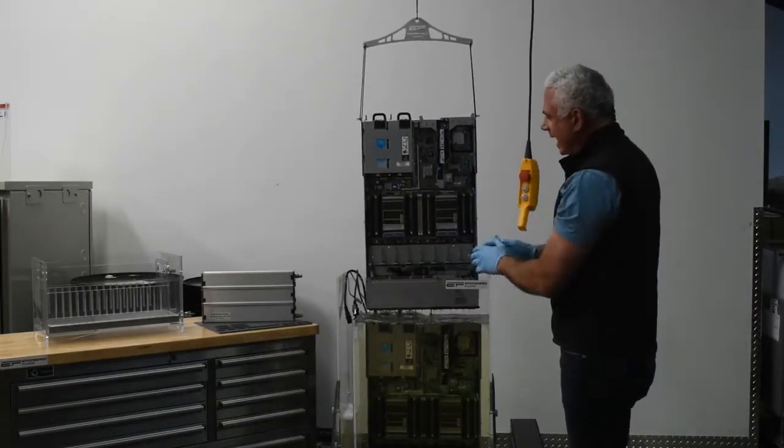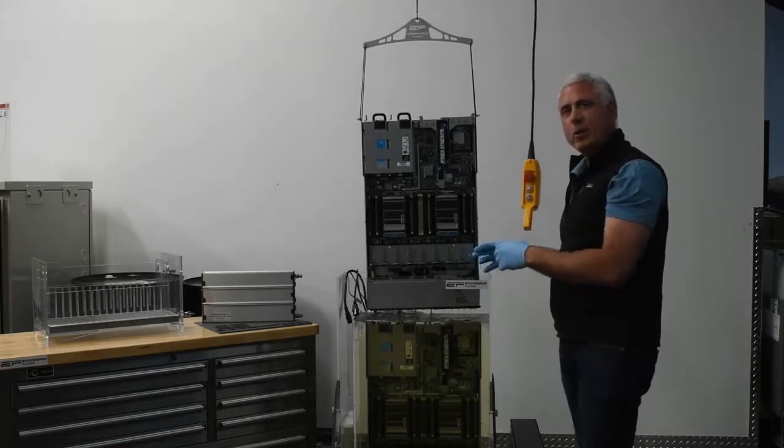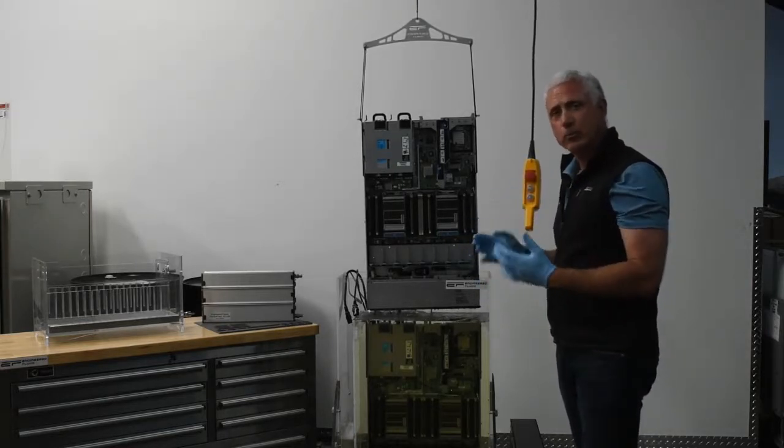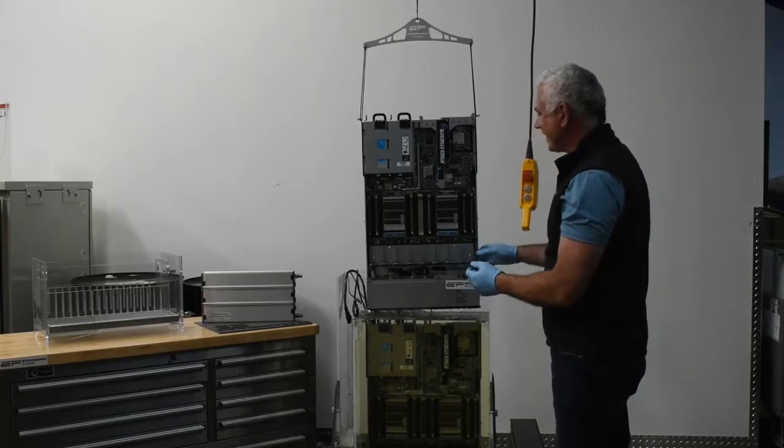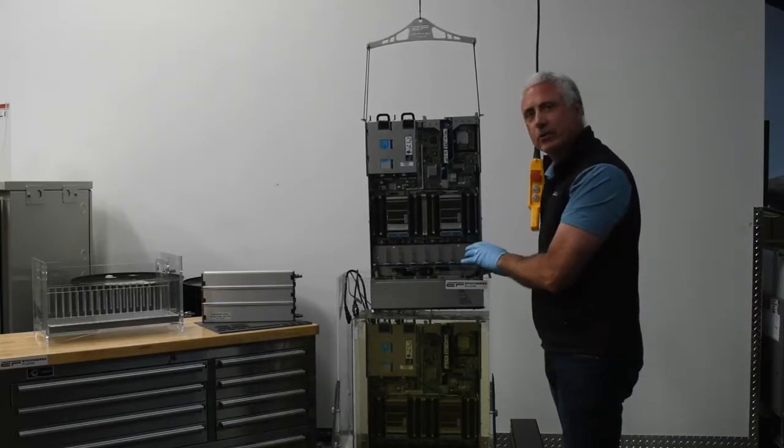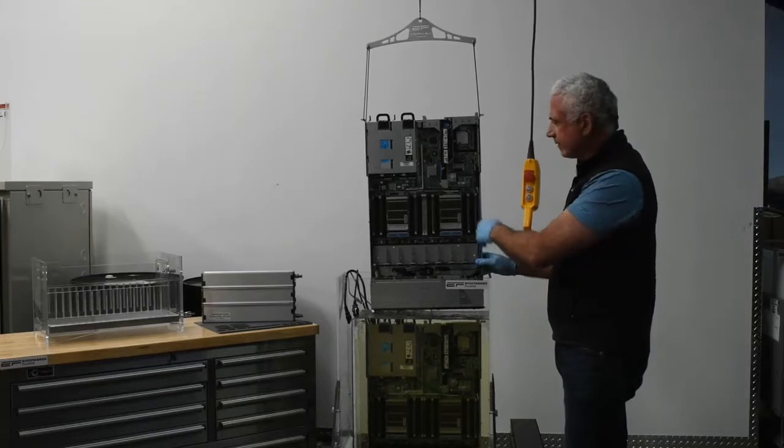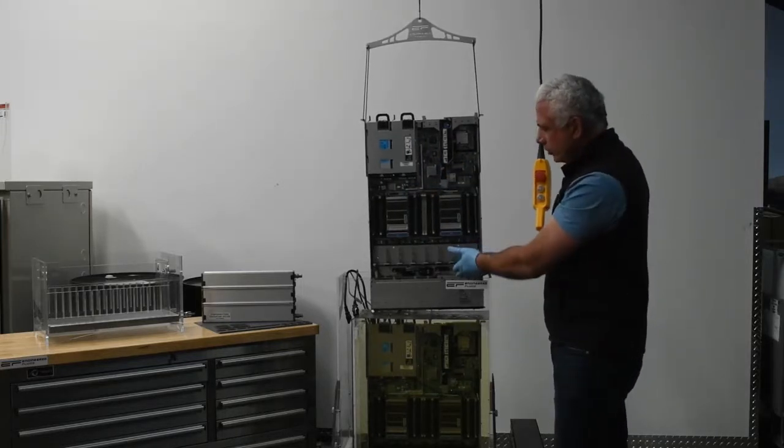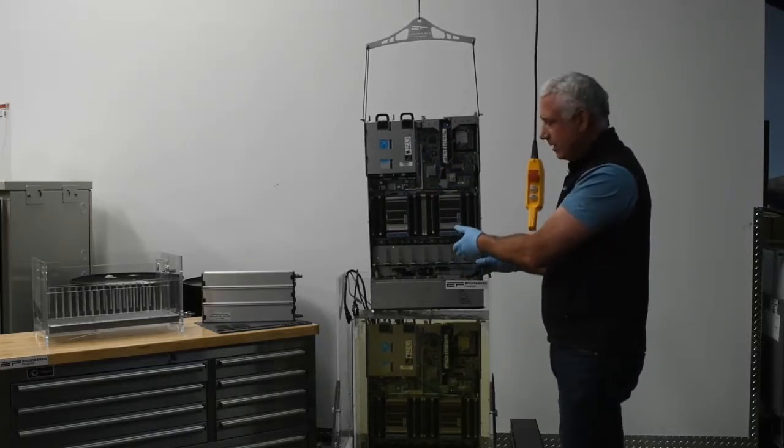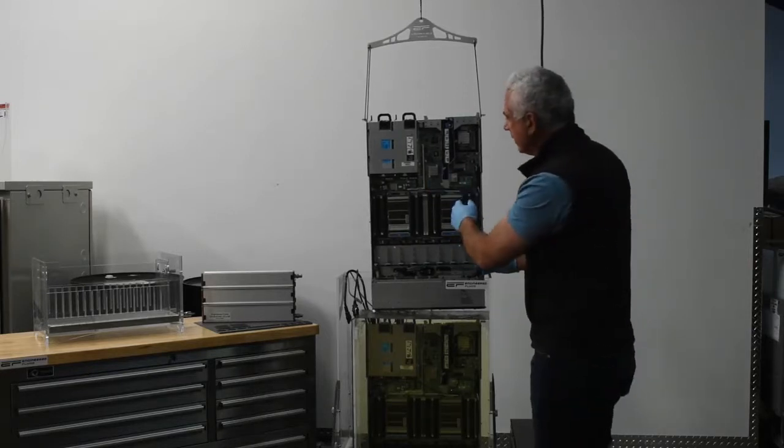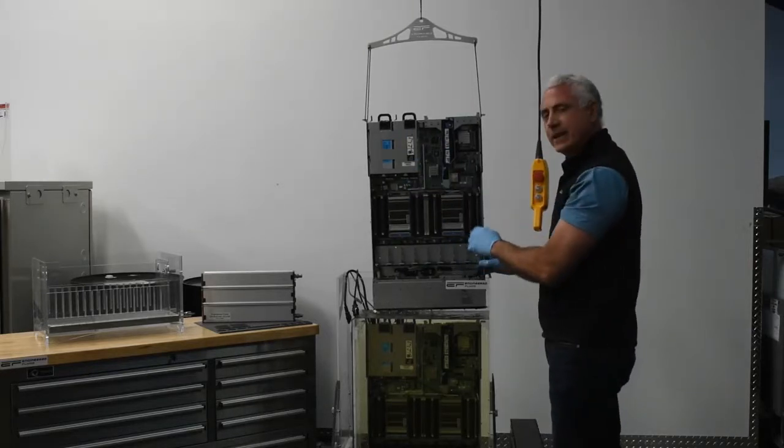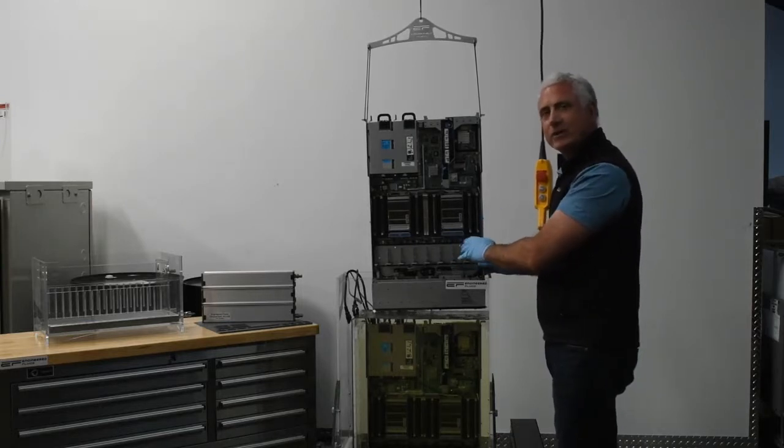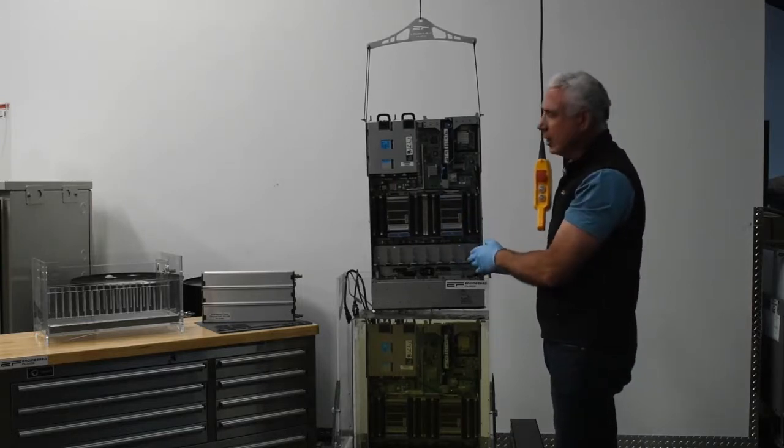Now we got a lot of discussion about where and how you should do maintenance. Our personal preference here at Engineer Fluids is to actually leave the server in this position when you're doing maintenance. And the reason is that you have full access to everything. You don't need to drain or dry the server because there's no reason—if you're doing any kind of standard maintenance any type of connections can be done without having to remove any of the fluid.